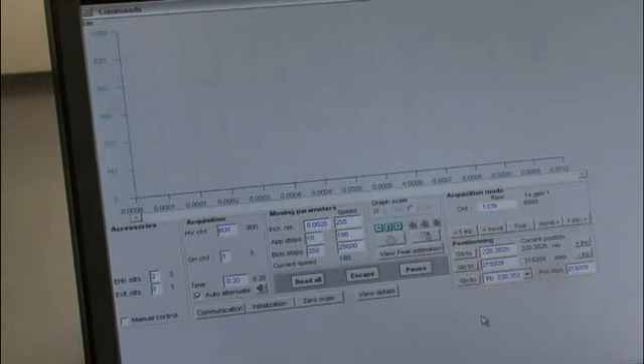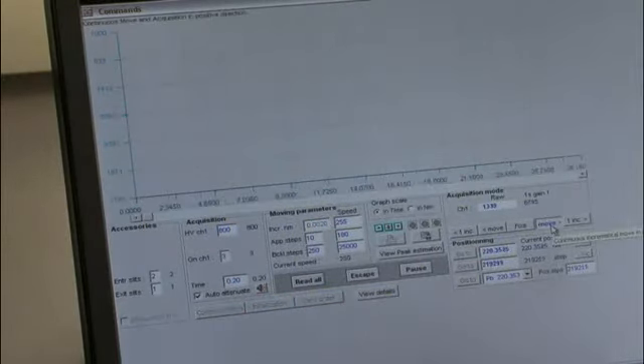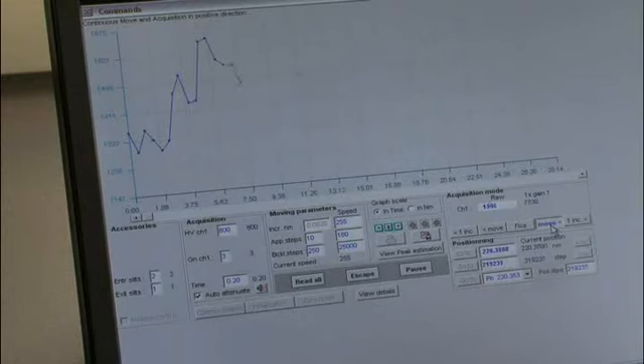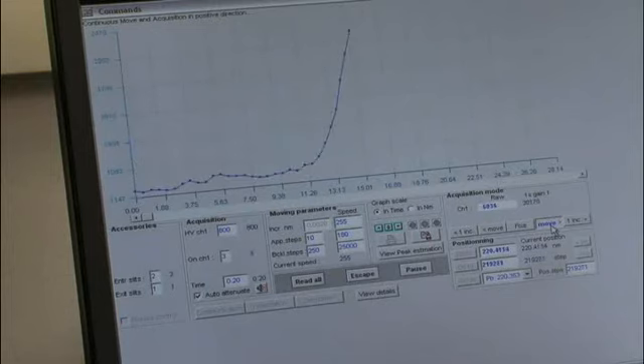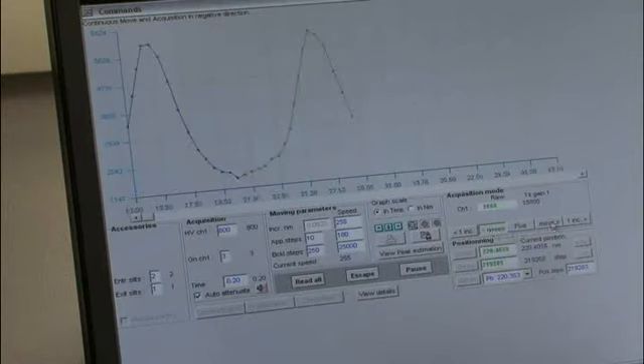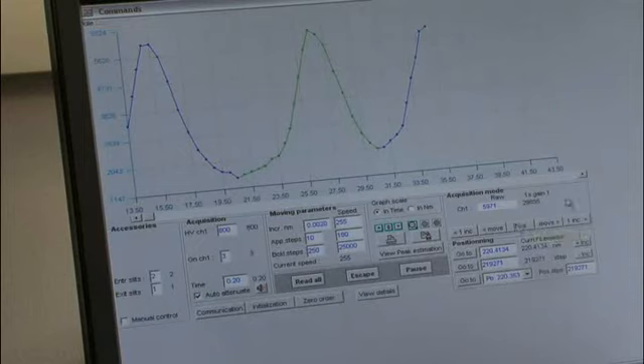Now the grating has moved to this wavelength, and it's not exactly on top of the peak. I'm going to tell it to move, and it'll find it. When it does, you'll see that it comes up. As it's scanning, it's going to come up and then come back down as it goes over the peak. It may not be up in wavelength, it might be the other way, but we don't know where it is yet, but it'll find it. All right, so that's coming up on the lead peak, and then it'll go over top of the peak and come back down. If I tell it to go back the other way, it'll go back over the peak again. Then I'm going to stop it on top of the peak.